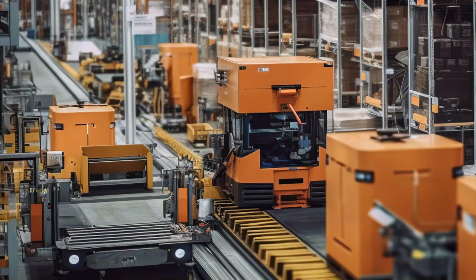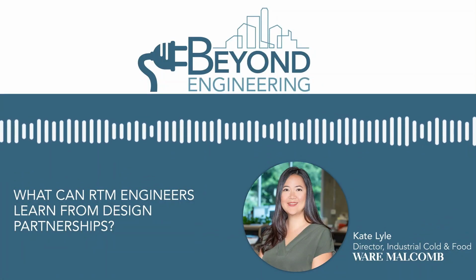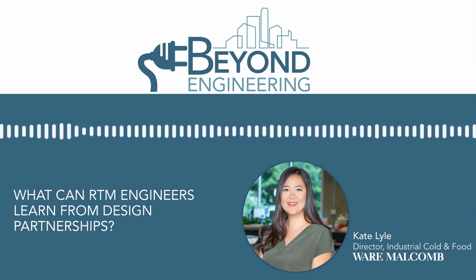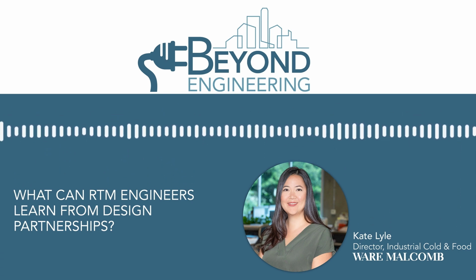You have to think about things like your slab design, right? A freezer floor is insulated, and so it's floating to a certain degree. And so the overturn on a very heavy, dense racking system is very different than if you can just bear on the ground a bit better. So there's all sorts of little things that we find that is unique to these cold storage buildings when integrating automation systems.